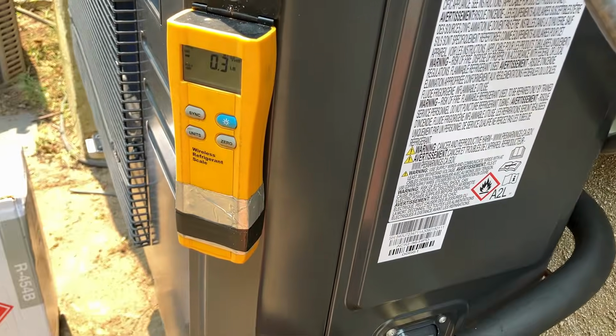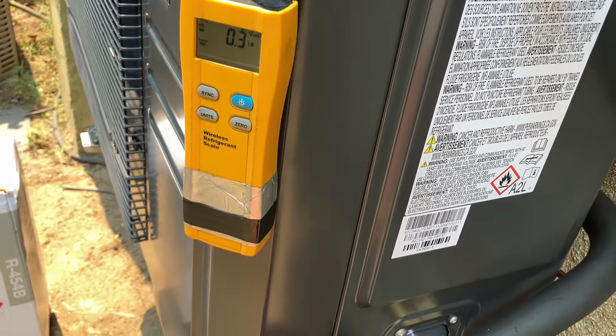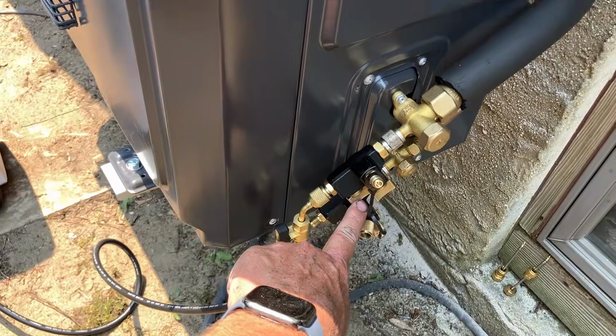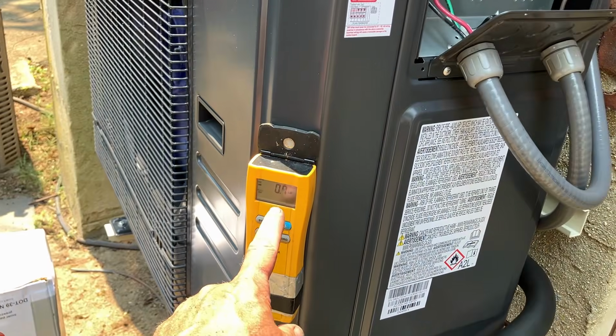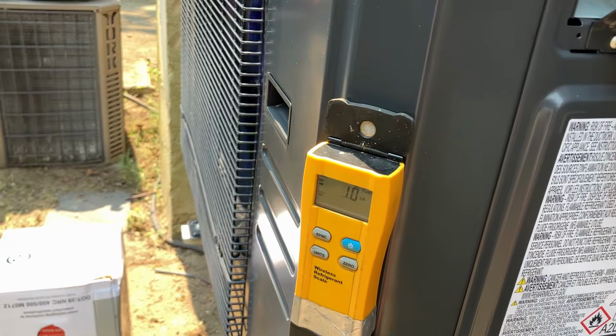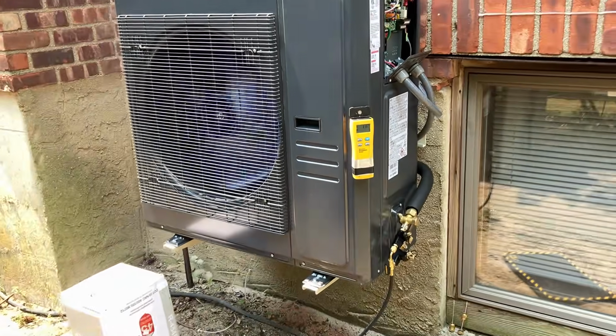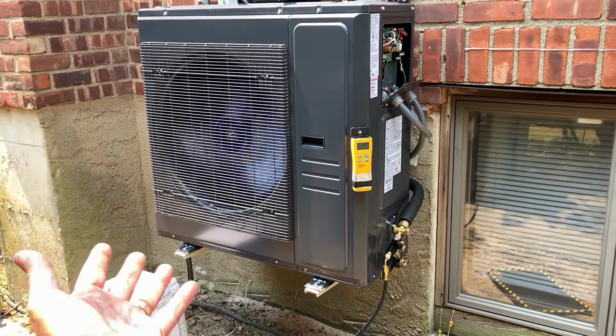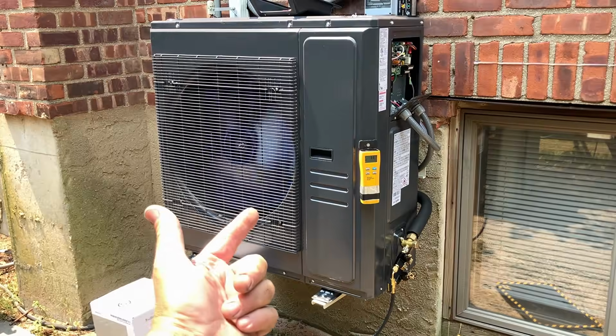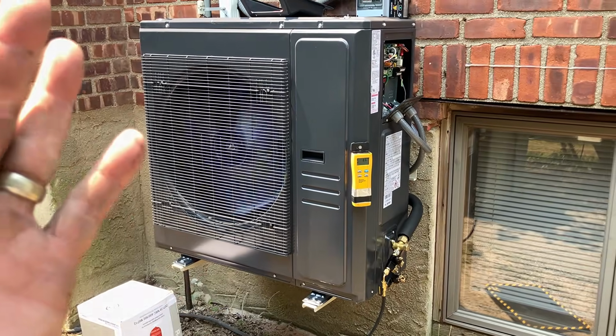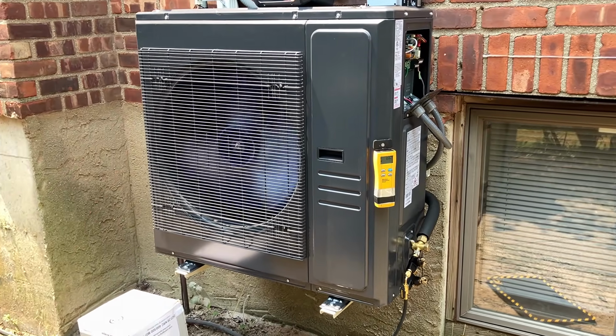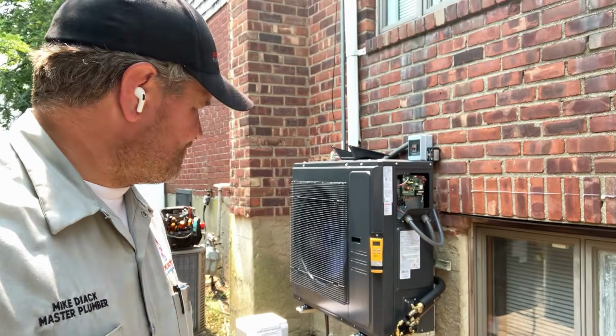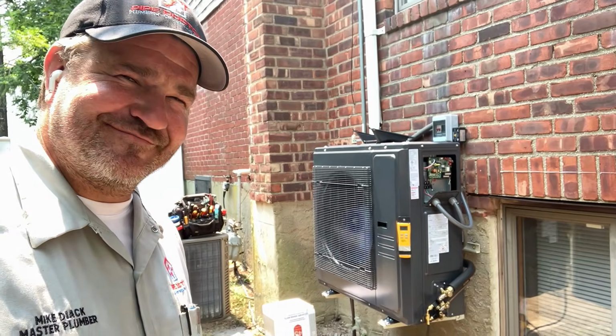Okay. Let's dump some more refrigerant into there. I'm opening up that valve. 0.4, 0.5, 0.6, 0.7, 0.8, 0.9, 1 pound. 1.1. We're good. It's an inverter, ladies and gentlemen, with DC motors on the outdoor and indoor unit. This thing is like a modulating high efficiency gas furnace. Thing is awesome. Whisper quiet, folks.